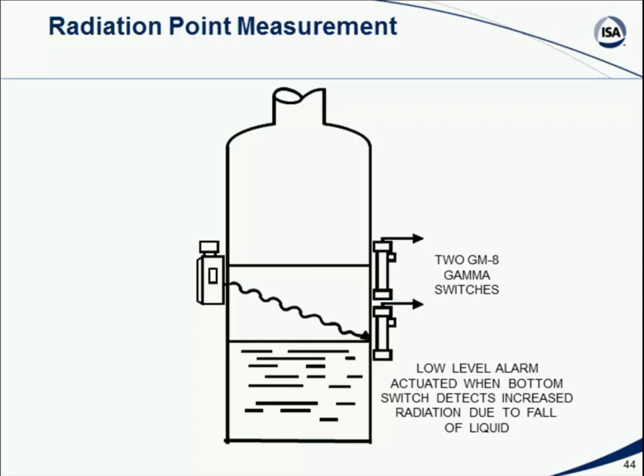If I then on the other side of this vessel or tank mount detectors, and there's a variety of different types of detectors, everything from Geiger-Muller tubes to scintillator devices. But if I place radiation detectors along the side of the tank on the other side, and I measure the signal strength of gamma rays that are striking them, then as the material in the tank raises up in level, it will start blocking the path of the gamma rays between the radiation source and these sensors, and it won't stop the gamma rays in most cases, but it will significantly reduce their strength or intensity. So as the level of the material in the tank rises or drops, by measuring the increase or decrease in the gamma ray activity measured by the different sensors up and down along the side of the vessel, I can actually get a rough idea of the level of the material in the tank.